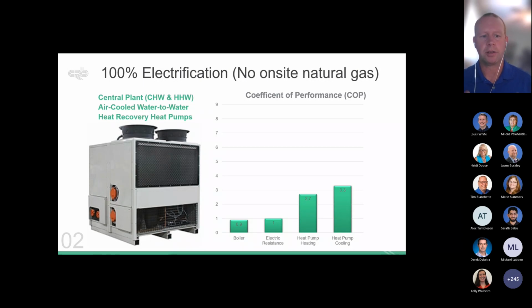A heat pump is no different than a chiller, it's just a reverse cycle. Oftentimes we just think about the rooftop package heat pump, but really it's a chiller run in reverse. For a lot of our facilities that are overcooling for dehumidification and then reheating, we have that simultaneous load year-round, and that's where this particular approach can really shine.